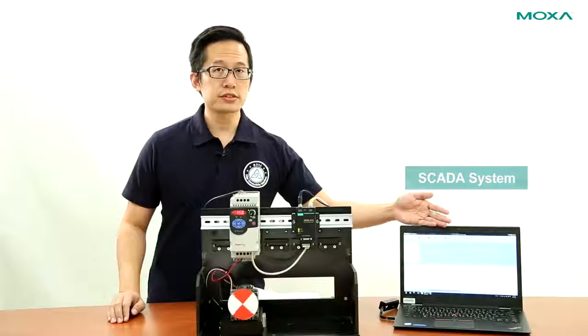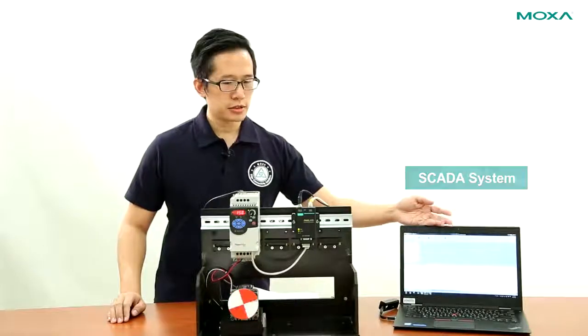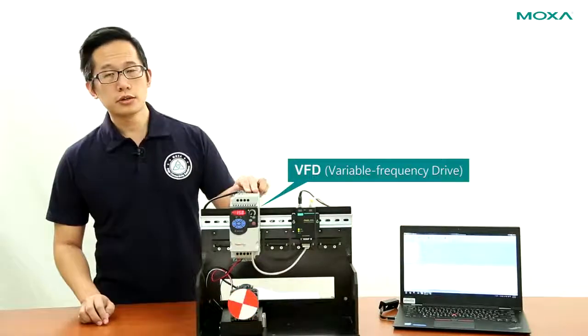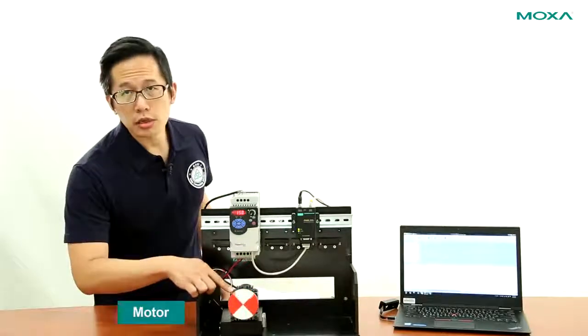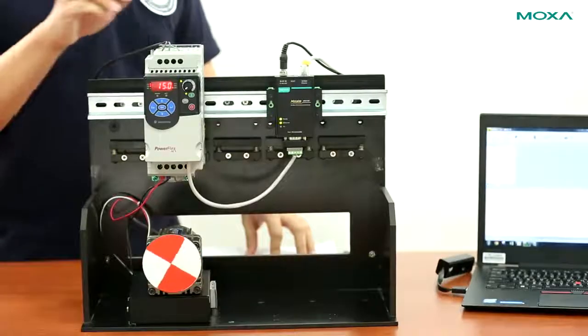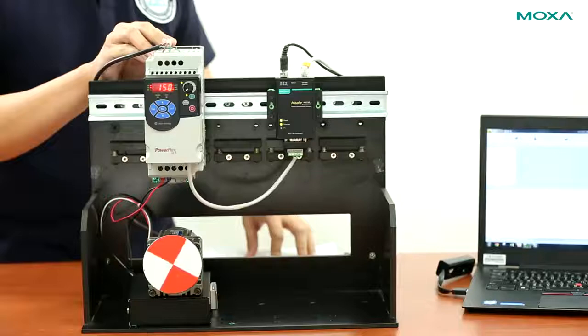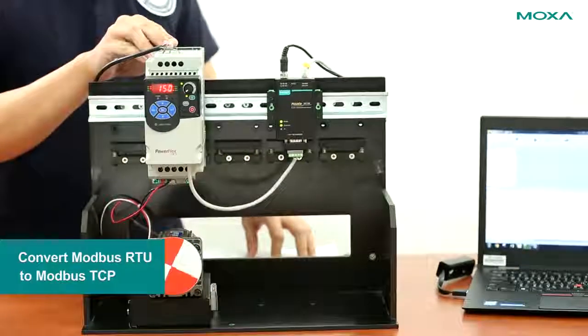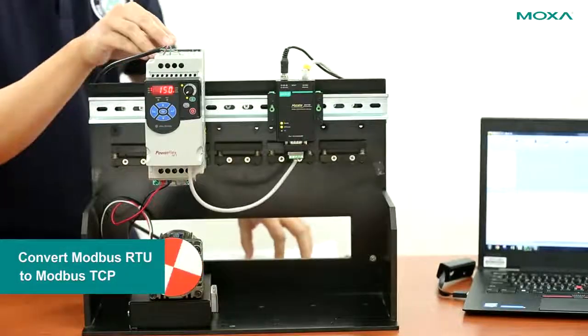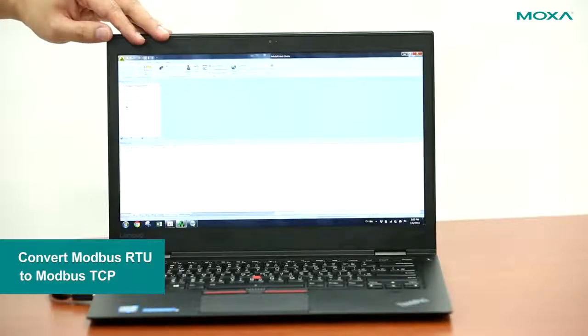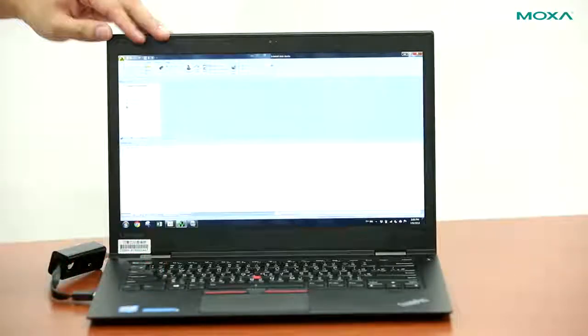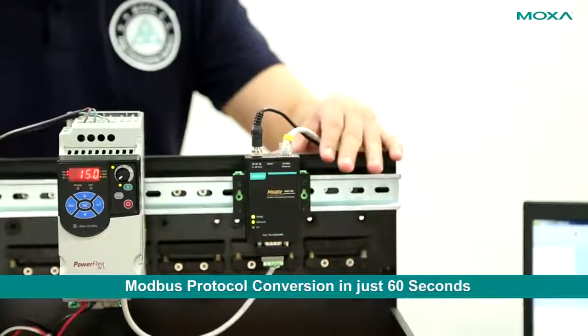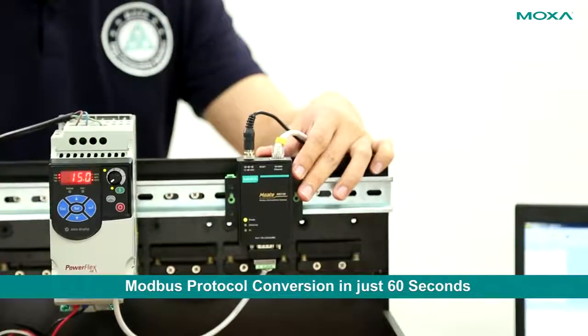Here, we have a PC running the SCADA system, and we have a VFD, which is powering a motor down here. In order to connect this VFD to the control network, we have to convert Modbus RTU protocol, which the VFD uses, to Modbus TCP protocol, which the SCADA system uses.